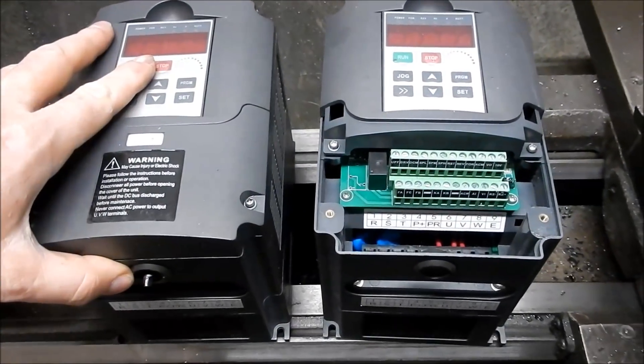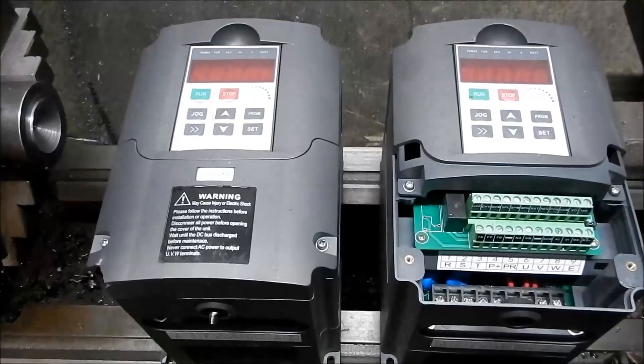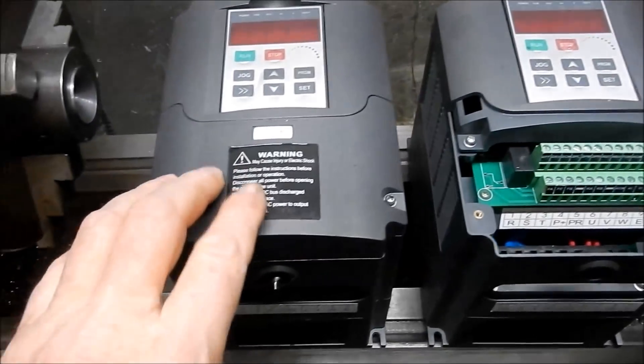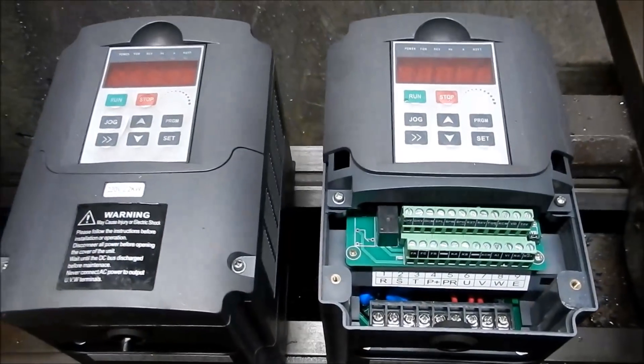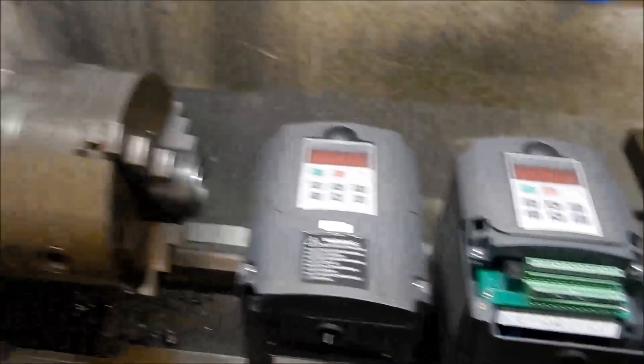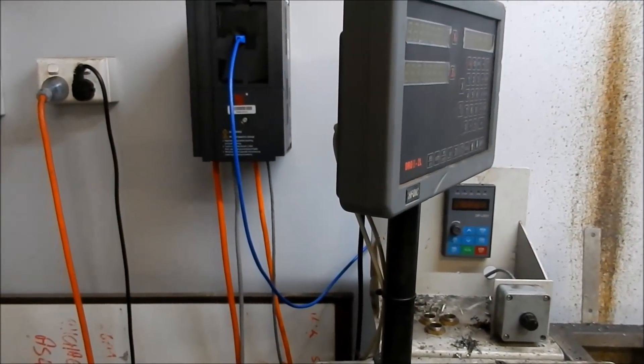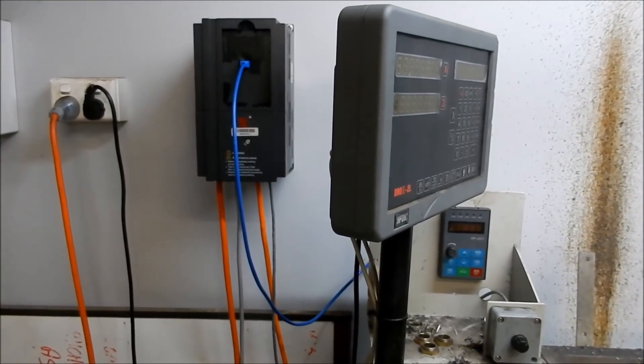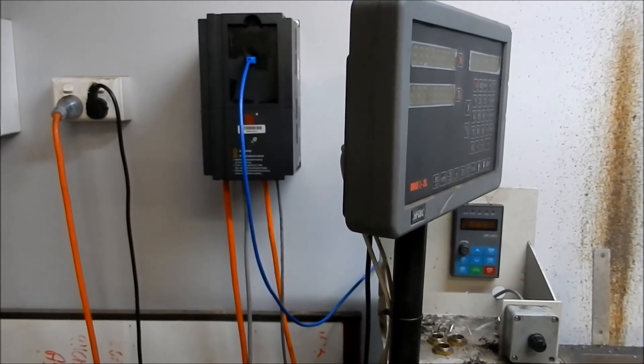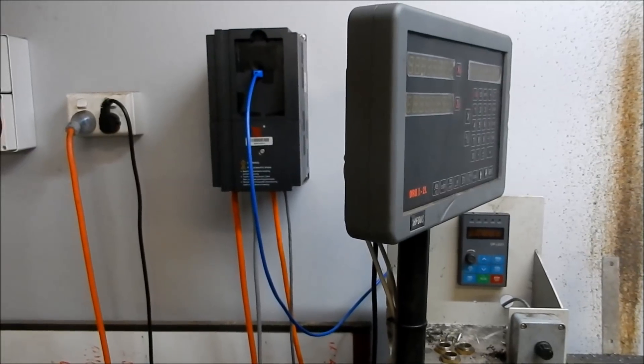I've now got two dead VFDs — these are the Huanyang Chinese units that sell for around $100 to $130. They've packed in within a few months of each other after about five years of use. We've got the new VFD up and finally running. Going through the manual was a little bit ambiguous with some of the instructions, but we got through it, with just a couple of little programming faults to overcome.